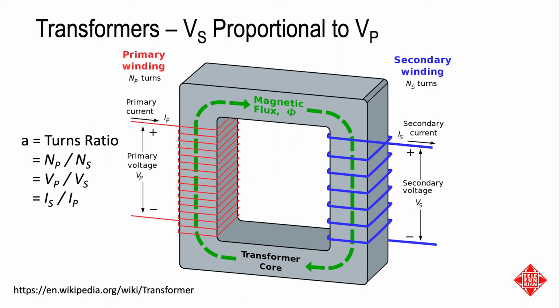A relatively simple solution might be available to us if we can simply modify the power transformer. Since the secondary voltages are determined by the primary voltage and the transformer turns ratio, it might be possible to change the turns ratio by removing windings from the transformer primary until we get to the secondary voltages we're looking for. Although not for the faint of heart, this isn't as crazy as it sounds.